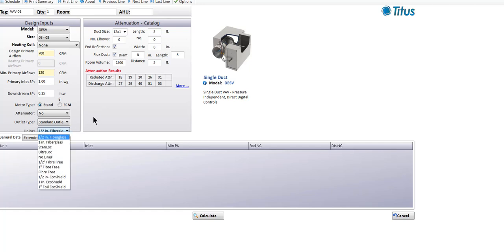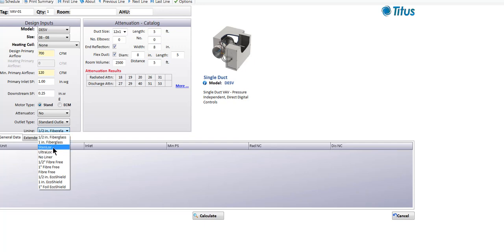The amount of sound level reduction you'll get from the optional attenuator is determined by the type of lining you select for the box. Since the integral attenuator is just an extended length on the one-piece casing, the type of liner determines what if any sound reduction we actually get. If we select a liner like half inch or one inch fiberglass, those will give us some sound reduction in discharge sound levels. If we go with a foil-faced liner like our SteriLoc or a dual wall liner like our UltraLoc, we're not going to get a discharge sound reduction.